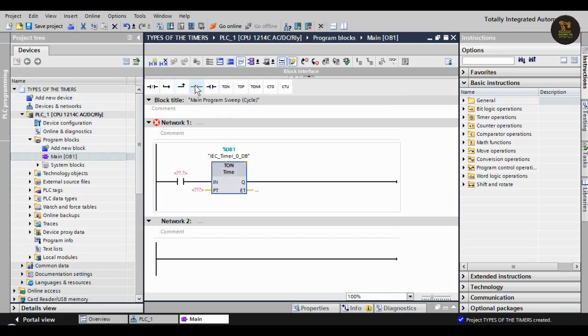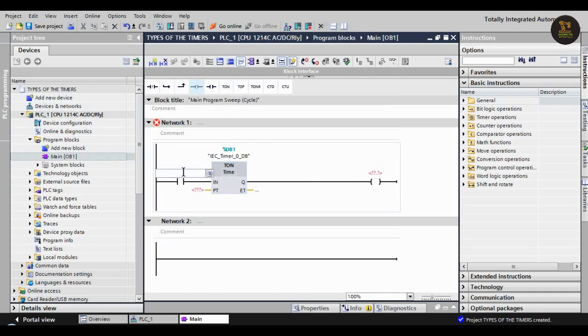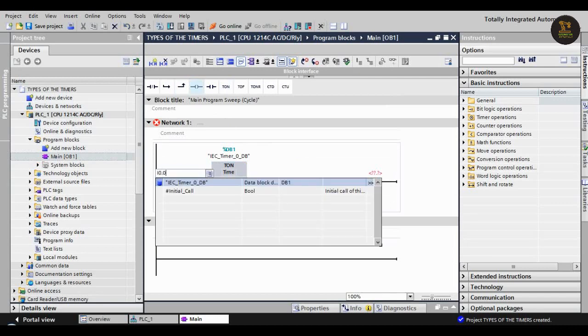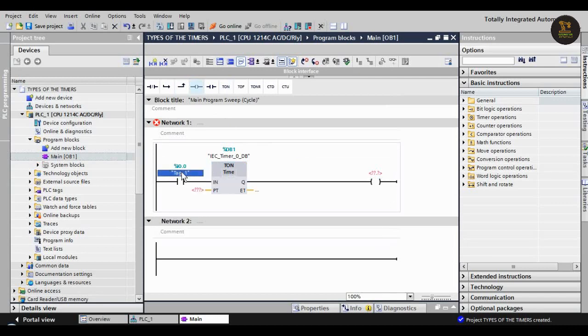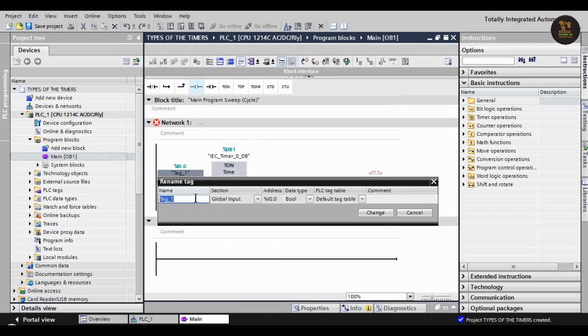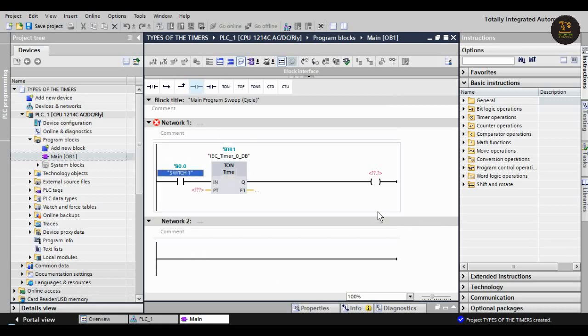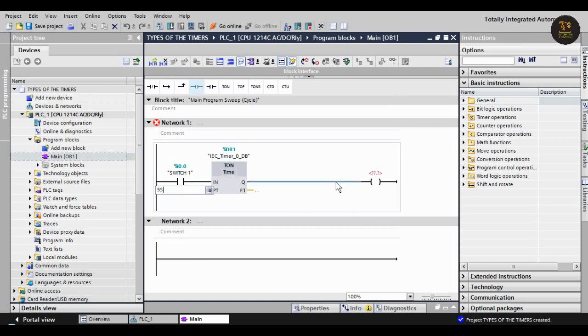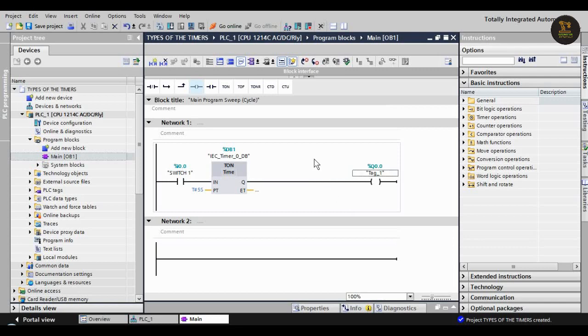Add an output and assign the input address I0.0, and assign a tag 'Switch One'. PT means how much delay we should give for the timer - I'm giving here five seconds. Then assign output Q0.0.